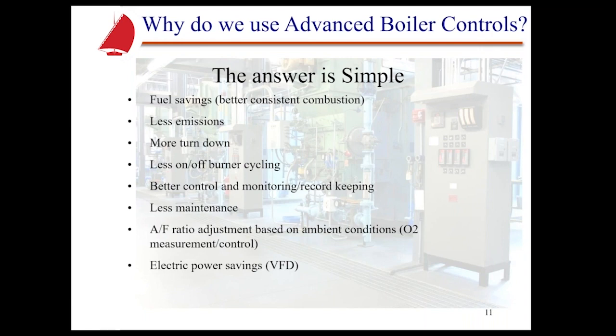but it doesn't give us as good a control as we could gain with a variable speed drive. And that's a huge advantage, particularly when we're trying to do a light off and we don't have real good, tight air damper closure. This can really be a huge advantage. So many times now we're seeing VFDs added to these systems for the actual electrical power savings.